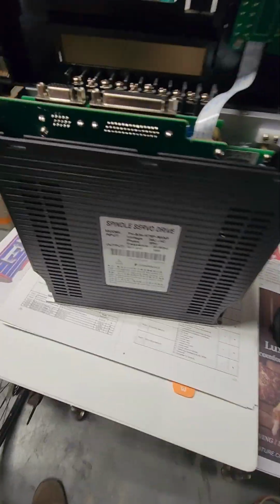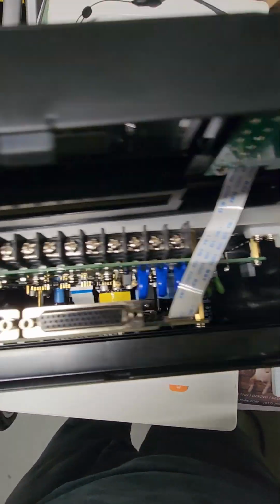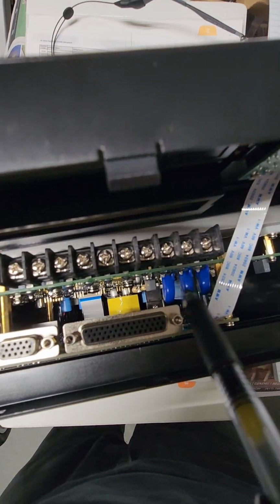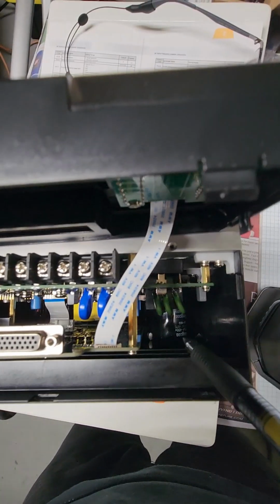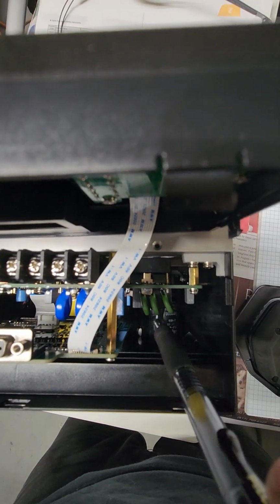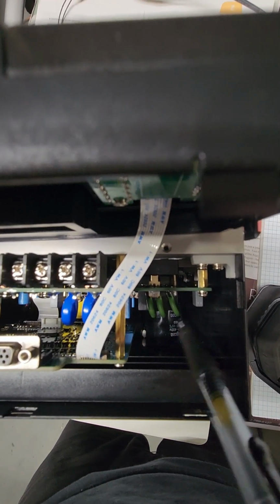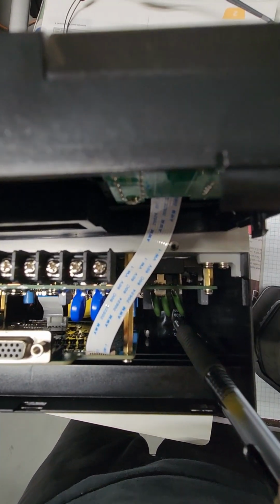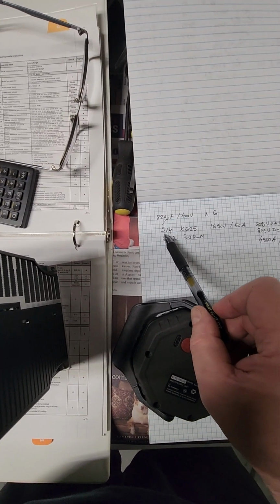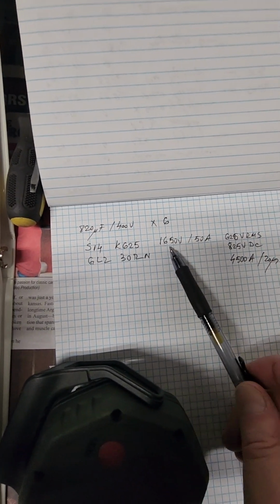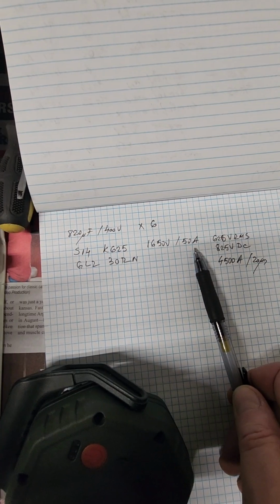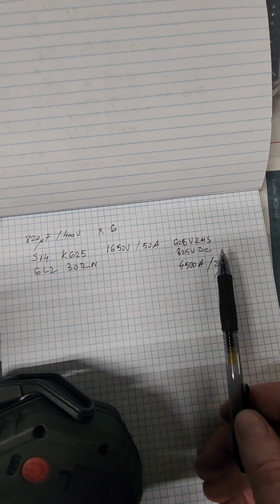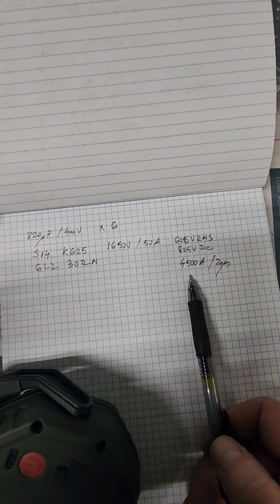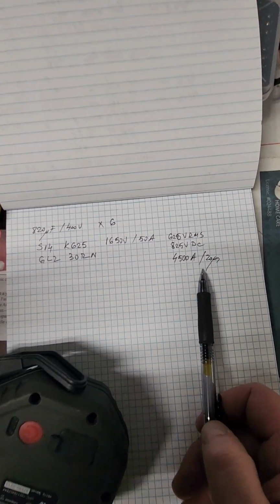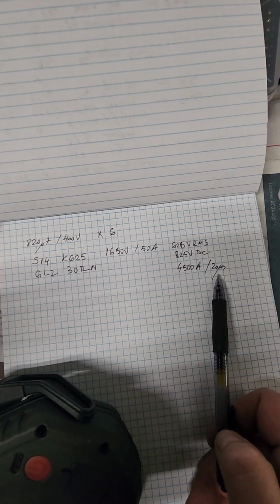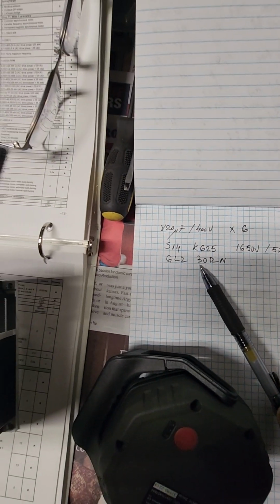I opened the drive to see if it has protection inside. So these 3 blues are varistors. They protect for voltage spikes. And those 2 greens are, I think they are NTCs, negative temperature coefficient. And those are to limit the current. This is the spec for the varistors, S14K625, 1650 volts and 50 amps for 625 RMS or 825 DC, and it can withstand 4500 amps for 20 microseconds. So this will take all the voltage spikes from switching or whatever, right? So that's gonna protect on the voltage mode. This is gonna protect on the current mode.